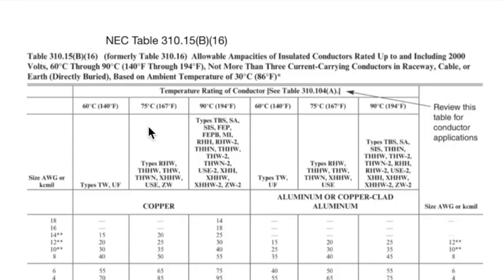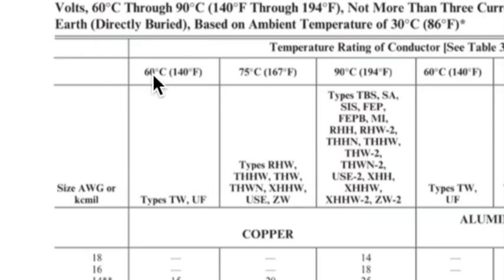These are your insulation types. We're going to talk more about that in one second, but I want you to see that each type of insulation is given to a certain temperature rating. 60 degrees Celsius, 75, and 90. THWN is good to 75. THHN is good to the 90, and TW is good to 60. Important to recognize that.